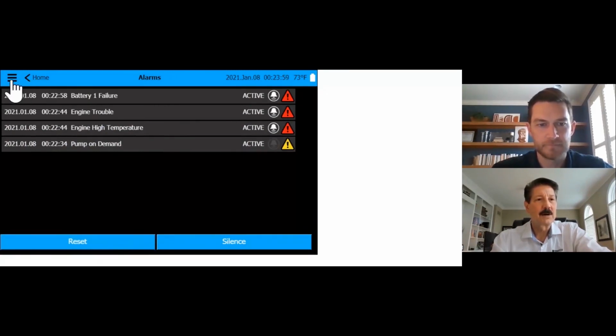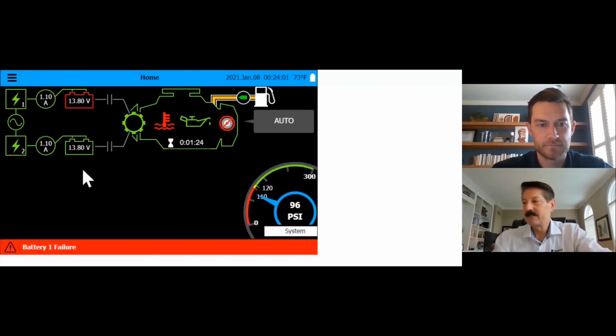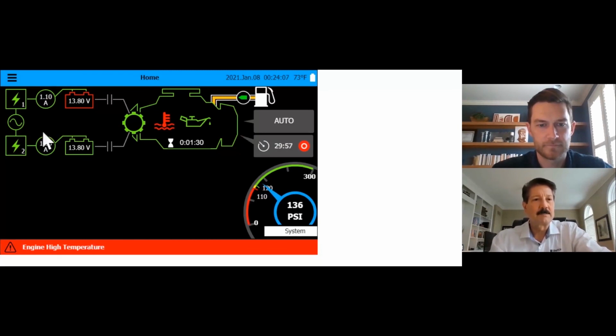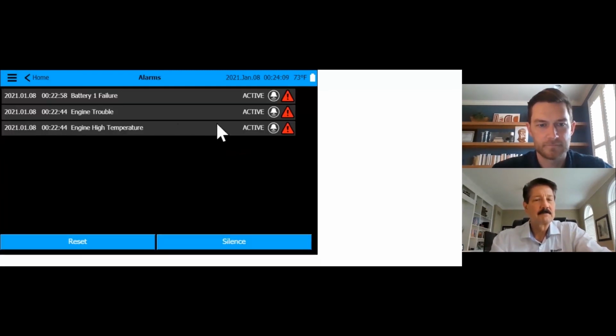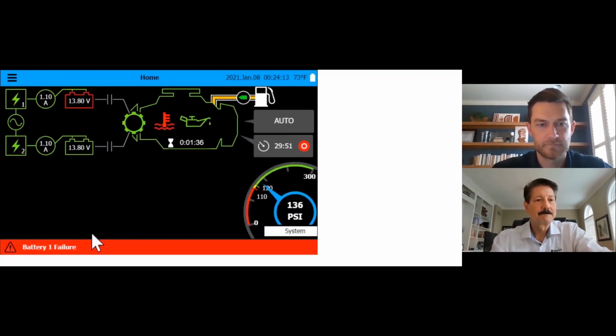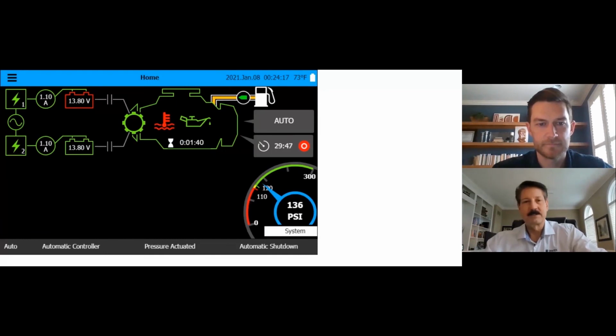Now, I could reset one quite easily. I could just bump up the pressure. And all that would do is eliminate one of those alarms. But we have three that are critical. They're red. So if I correct those a little bit, let's see. Let's do this one. Let's do that one. Both of them are clean. Yep. Now, the worst case.